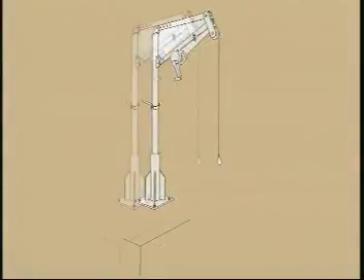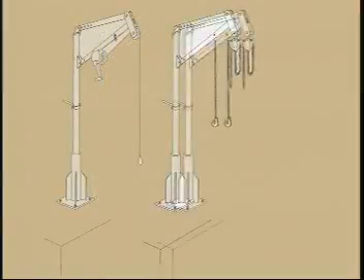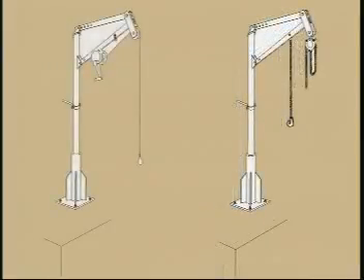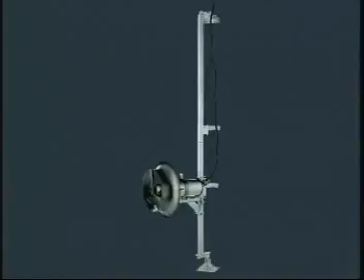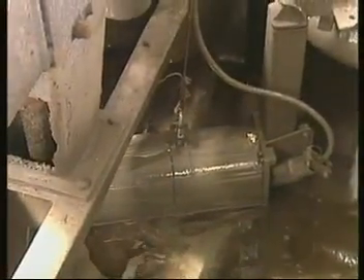To support your installation, ITT Flygt can provide suitable lifting equipment such as lifting davits, winches, blocks, tackles, and chains. We can cover a wide range of different weights. The mixer can be installed on the guide bar in a horizontal position or with a standard angle of plus or minus 10 degrees or plus or minus 20 degrees. Check that the mixer travels up and down the guide bar easily before lowering the mixer to the required working depth.